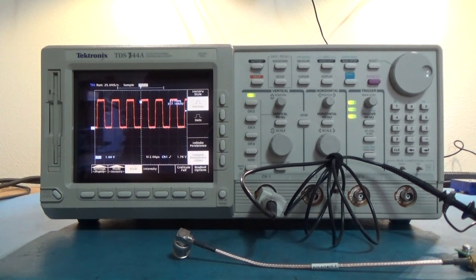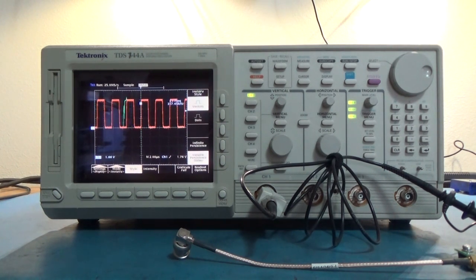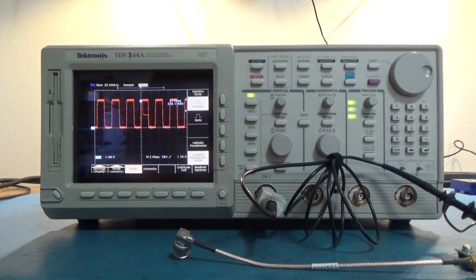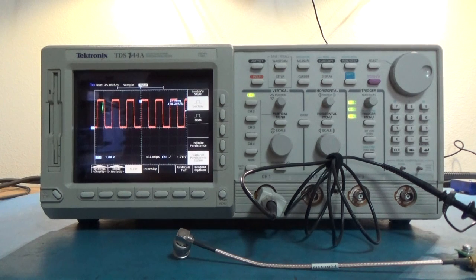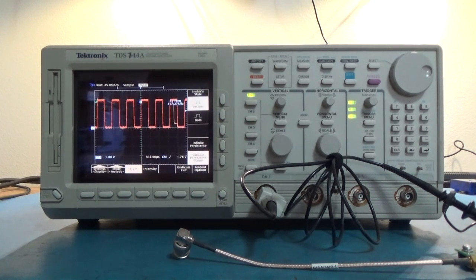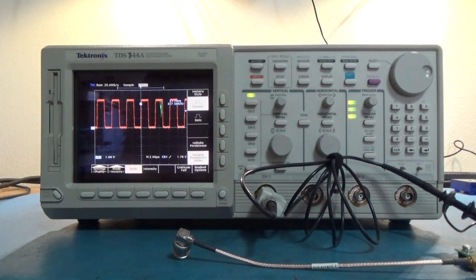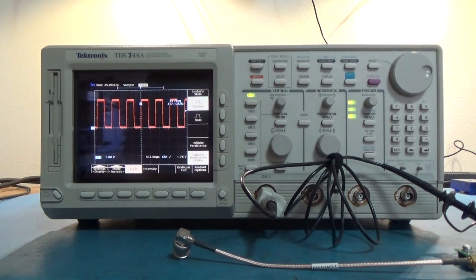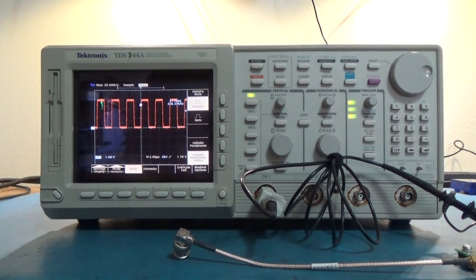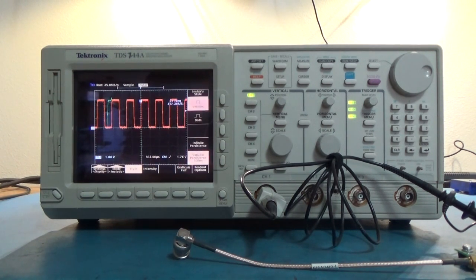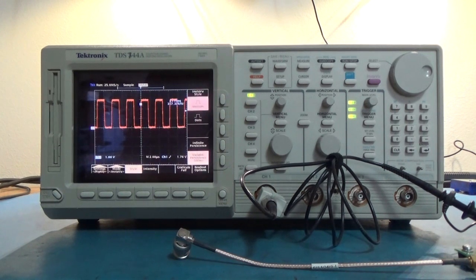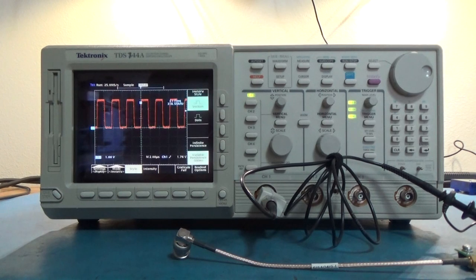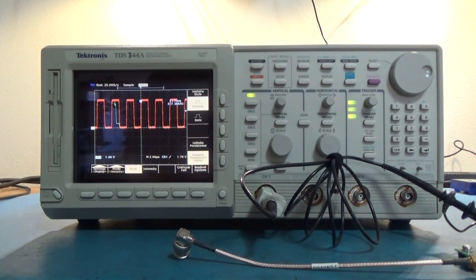So the scope is constantly acquiring waveforms, constantly displaying them. It's a circular database thing. Always writing, always reading, never really stopping. I don't know if you can really believe Tek with 400,000 waveforms per second. I think it's a marketing thing. By the much later 754Ds, I think they were talking about 200,000 waveforms a second, not 400,000 like this one.